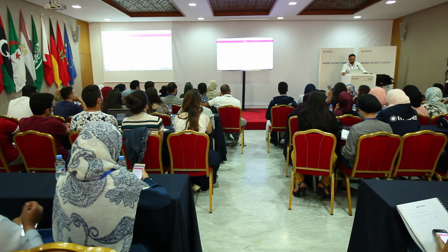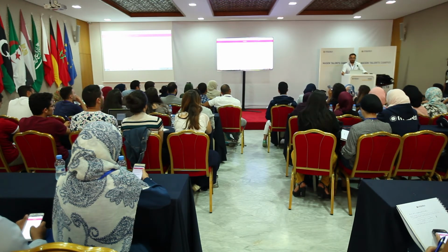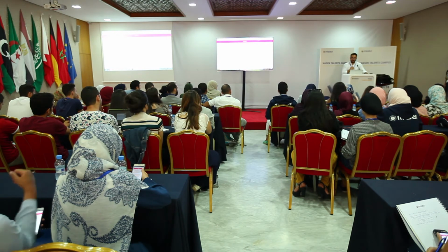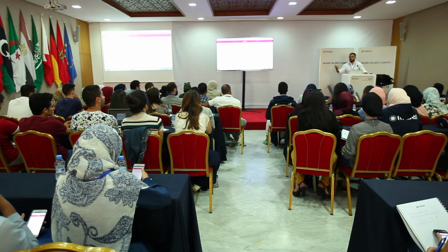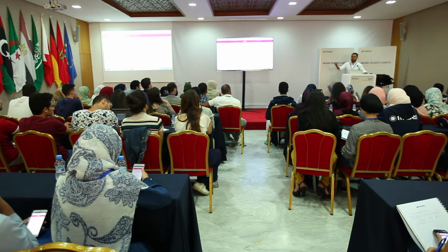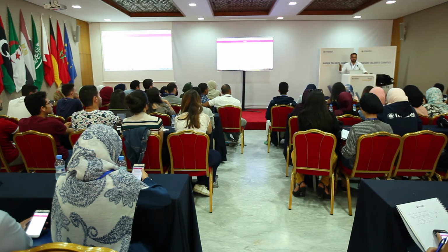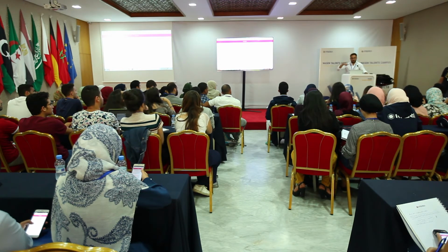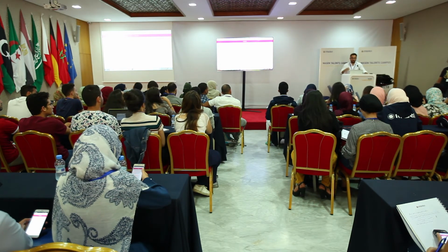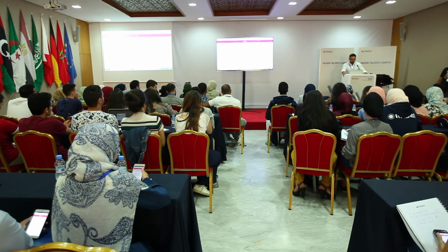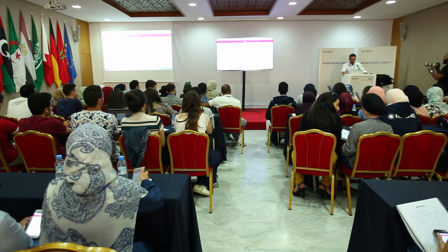If my collector system, my solar tower and so on, is able to bring a fluid to 600 degrees, then the most efficient cycle that I know of today that can operate at 600 degrees is a steam cycle. That's the reason why most of them are steam cycle based. If the system were operating at 1,000 degrees instead, it would be more like a gas turbine cycle. But steam is the most common because steam cycles are the most efficient technology when operating between 300 and 600 degrees, and that's where all the know-how and materials we have today for CSP plants are.